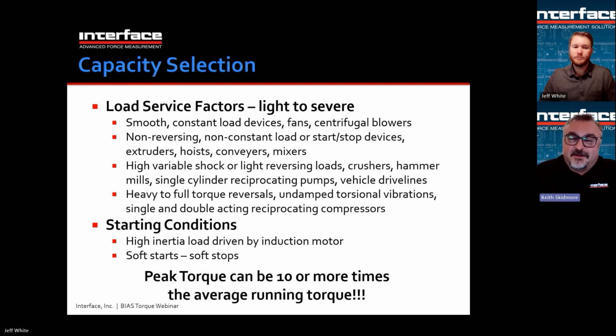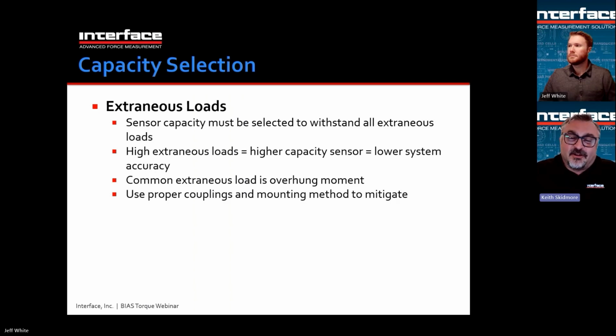So moving on. Extraneous loads. These cause errors. So we talk about using couplings. Sometimes extraneous loads are not able to be eliminated. For example, with a reaction torque sensor with a large mass, say, hanging on the torque sensor, it might be that that extraneous load as a bending moment or overhung moment cannot be avoided. So what has to be done is you have to size the sensor up. They typically have a rating for allowable overhung moment, and you need to find a sensor that can withstand the amount of overhung moment you will apply. And it could be that that makes the sensor much, much higher capacity than you may want, but that's just how it works. You can't have a very small capacity sensor withstand a very high overhung moment, for example. So you may have to size up the sensor due to extraneous loading also.